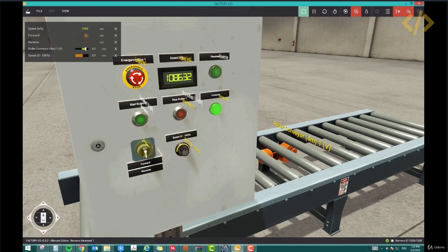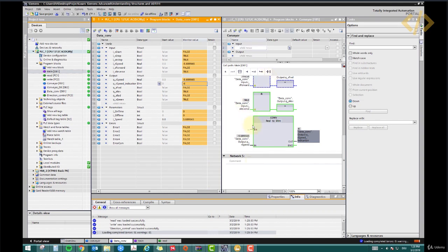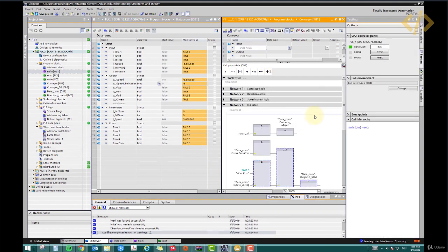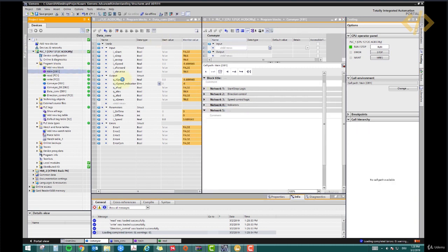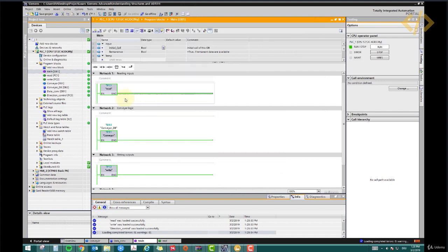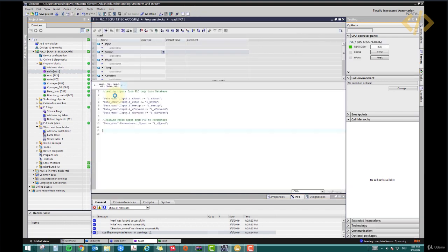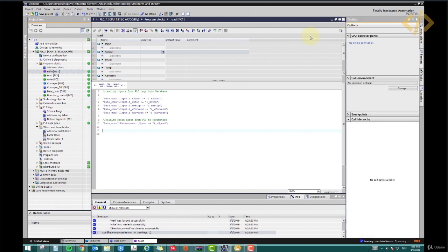But I hope in this lesson you have understood how to use indicators and how to use basic programming instructions in different DBs and using FB and FC. So if I just want to conclude this logic, let's go to the main logic. We have initially the read function. This read function is reading the inputs from the PLC and moving them into a data block, which is defined for the conveyor.